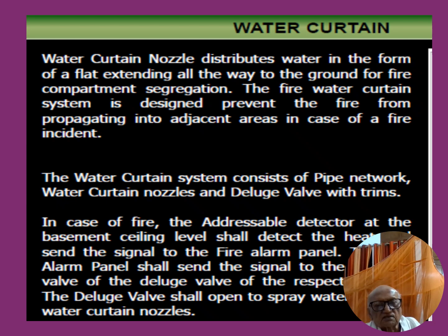Friends, water curtains are to be provided in certain cases. Water curtain nozzles distribute water in the form of a flat sheet extending all the way to the ground floor for fire compartment segregation. The fire water curtain system is designed to prevent the fire from propagating into adjacent areas in case of a fire. The water curtain system consists of pipe network, water curtain nozzles and deluge valve with trims.